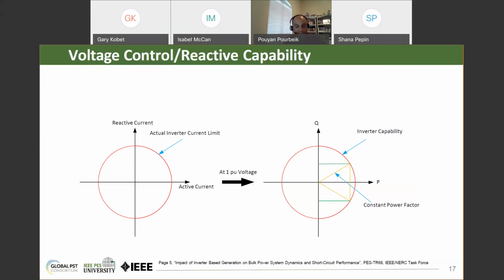Now, the issue was, again, because of no clear definition globally of what we expect in terms of reactive support, in some cases people would do what you see on the right-hand side drawn as a yellow triangle, where they would allow a constant power factor from full load to no load. So you only get the limited reactive capability you see in that yellow triangle, whereas you have more available. So at the very least, you should be able to get what's shown by the green box, where you get a constant level of reactive current through the operating range of the device.